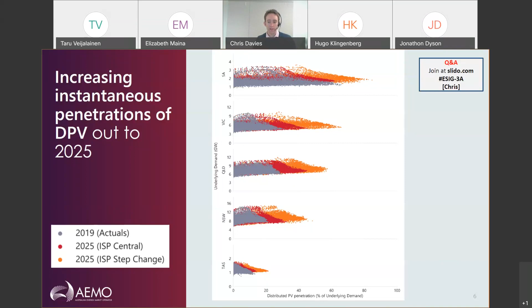So from a system operator's perspective, the challenges of managing increasing levels of distributed PV span a number of areas. First is the response of distributed PV to power system disturbances. So in particular, the potential contingency size we get if a large volume of distributed PV was to disconnect as a result of a system event. Next is the erosion of operational demand during the middle of the day, which creates a number of challenges of its own. So firstly, maintaining a sufficient level of operational demand to support the minimum loading levels of the minimum number of synchronous generators that we need to have online for system services that can't be served by distributed PV. So things like system strength, inertia, and some frequency control services.